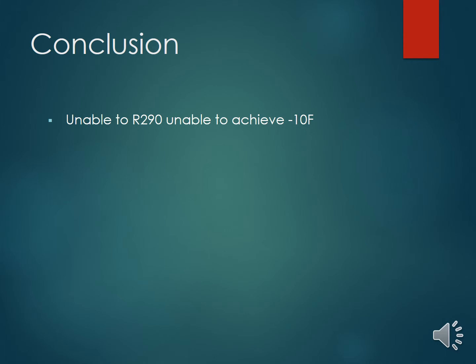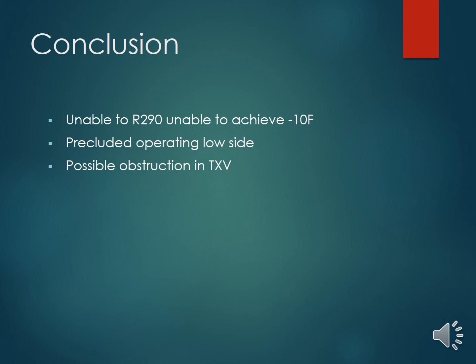Unfortunately, the R290 thermal expansion valve could not be adjusted to achieve the minus 10 degrees Fahrenheit in the interstage heat exchanger without being able to properly condense the R170. The low side operating system could not be run for more than a few seconds. The possible cause of this was an obstruction in the thermal expansion valve. Replacing the thermal expansion valve would most likely have alleviated this problem. If the system was run again, it would have been closer to the results calculated in the paper.